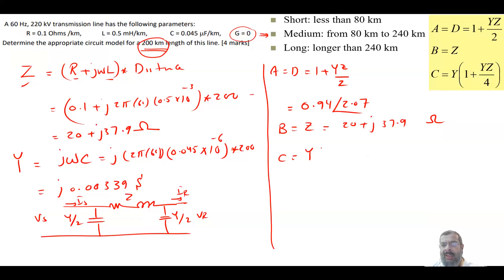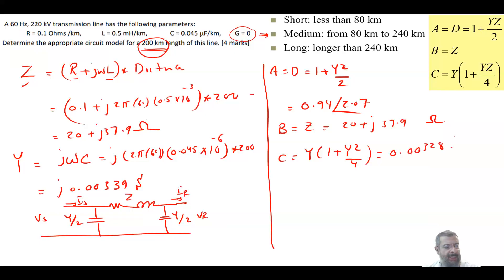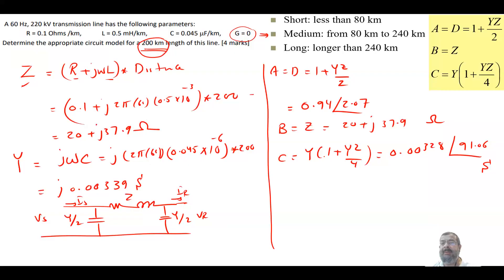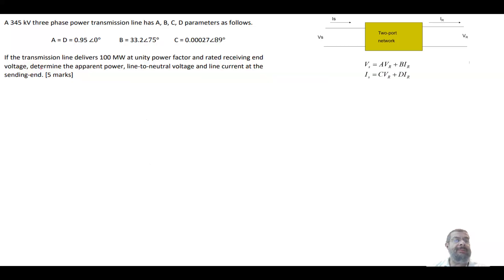C equals Y × (1 + YZ/4). C typically represents the shunt element and is usually a small value — here it equals 0.00328∠91.06° siemens. For a short transmission line, C is zero, so as the line gets longer, C increases gradually. That concludes this part; now let's look at the last part.